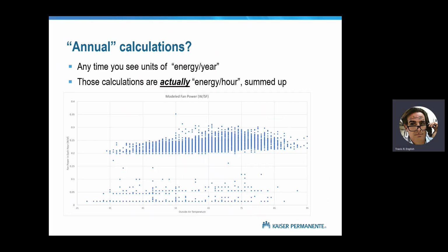If you have the model, then you can look at the fan power in each hour. We like to plot it like this. Outside air temperature is on the x-axis and watts per square foot of fan power is on the y-axis. This is a different building, by the way, but you can see from 0.2 to 0.3 watts per square foot of fan power, most of the points are falling in that range.